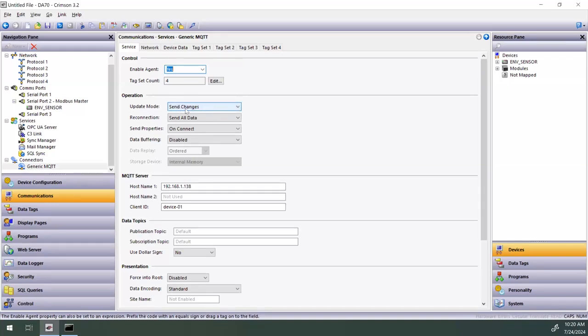Now, another major benefit you get from MQTT is data buffering. If I have this DA70 configured as an MQTT client, and I'm transmitting values to the broker, some important values we're monitoring over a long period of time, and let's say my connection to the broker goes down, for whatever reason, somebody accidentally cut the Ethernet cord, we've lost connection, we're no longer transmitting our values to the broker.